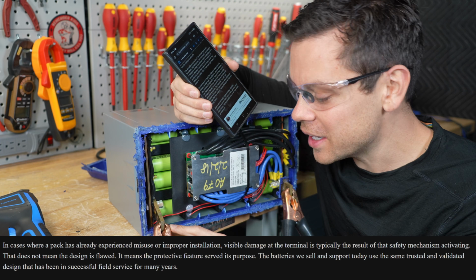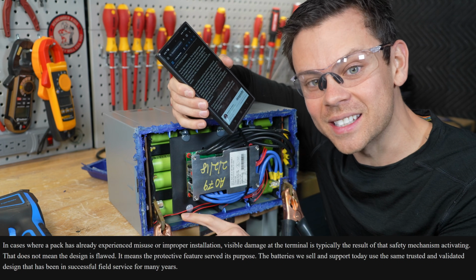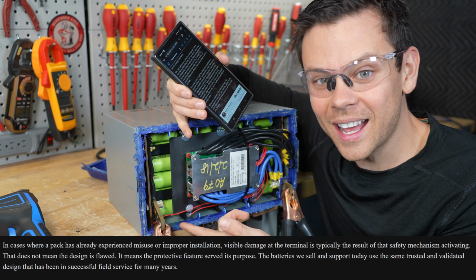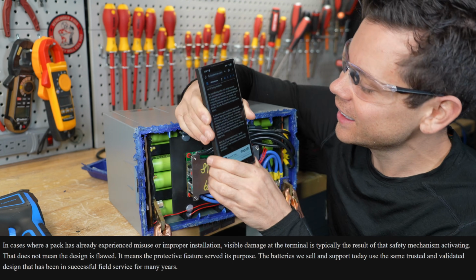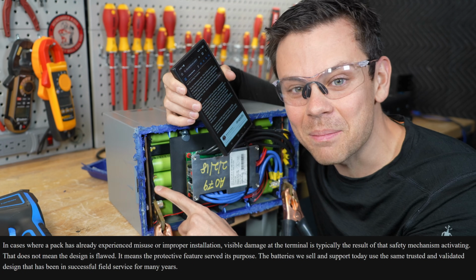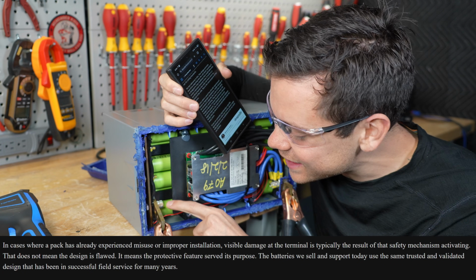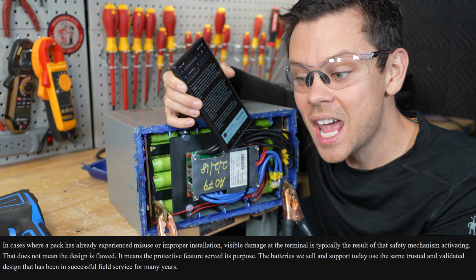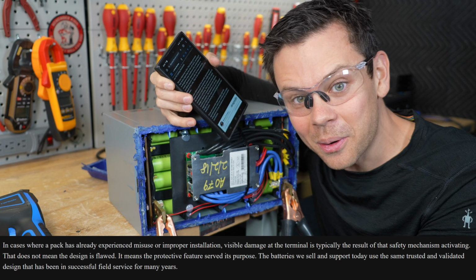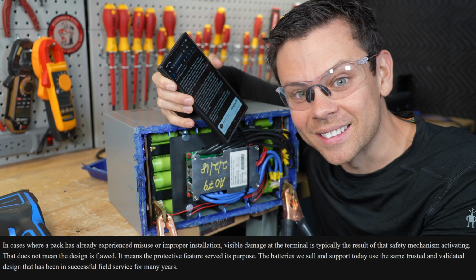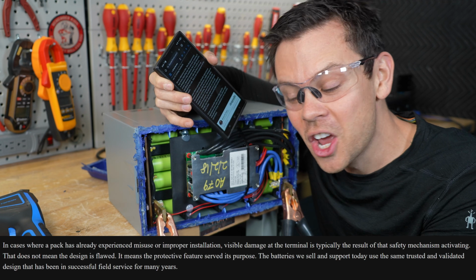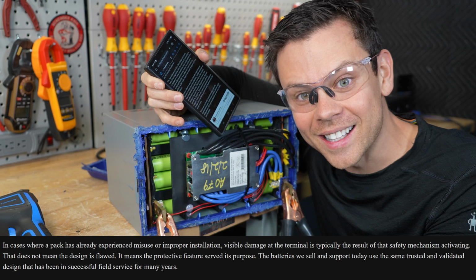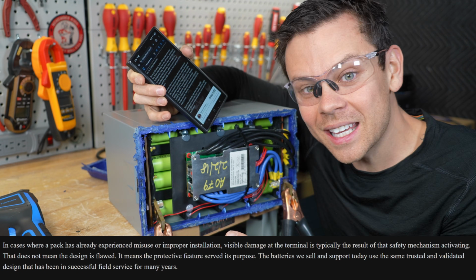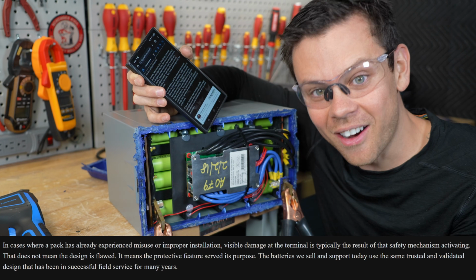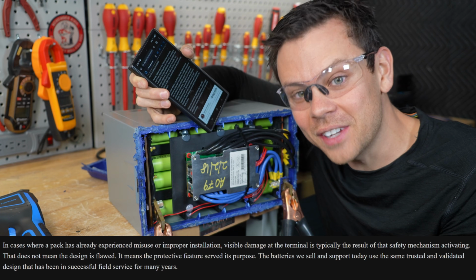If this safety feature is to be relied upon, it should disconnect. Are we getting that? Absolutely not. Their logic is if this plastic melts a lot, it will disconnect it because it has a bad connection. That bad connection is the problem. It is not disconnecting. It's creating a bad connection, which causes things to get hot. And the only way to find out is to put a heat camera on it and see if it's getting hot. That's not a protective feature.